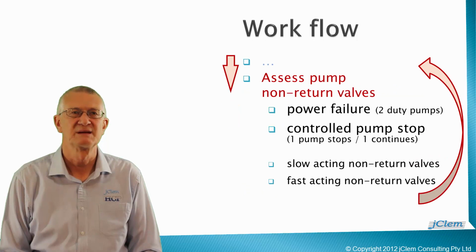future work. Project teams will not have assessment and selection of non-return valves in their scope of work on every engineering project. The case study will show you how to assess some typical pump station scenarios, including a power failure event, looking at the consequences of slow-acting non-return valves, and the improvement created by fast-acting valves. And then a more regular event of one duty pump stopping automatically while a parallel duty pump continues to run.